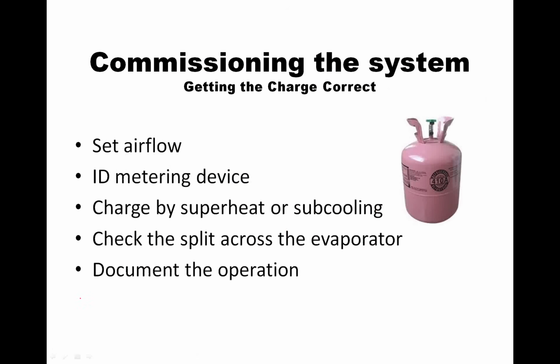When we commission the system, to get the correct charge, we have to do a few things. Number one, we have to set the airflow. We have to identify the metering device, so we need to know what type of metering device we have. We're going to charge it by superheat or subcooling, and then we're going to check the split across the evaporator. I'll cover that in some more detail. Then we want to document the operation.